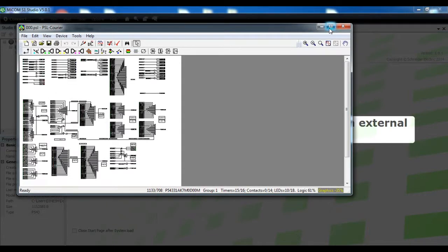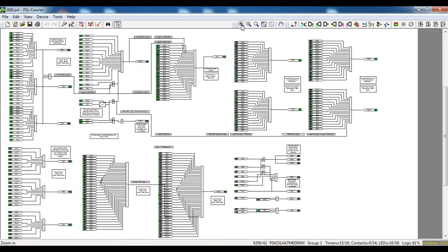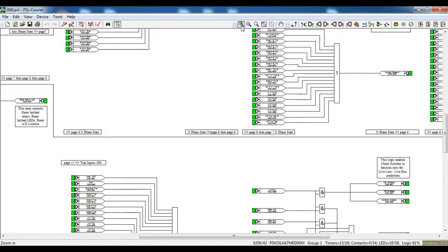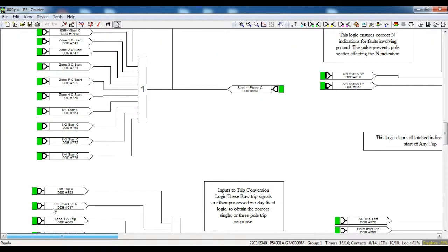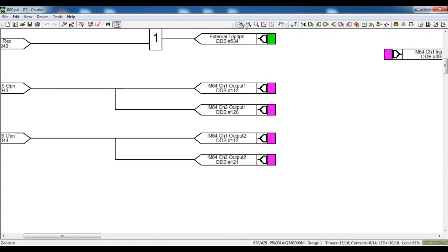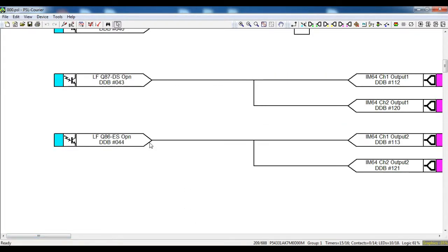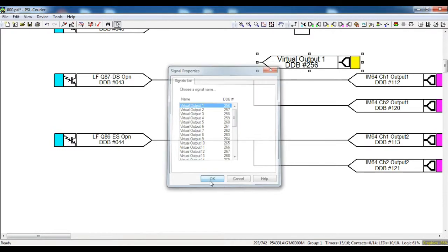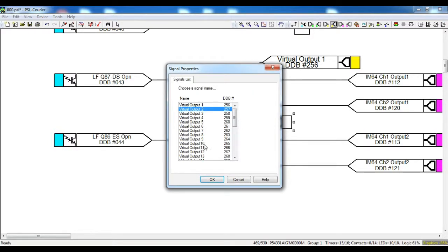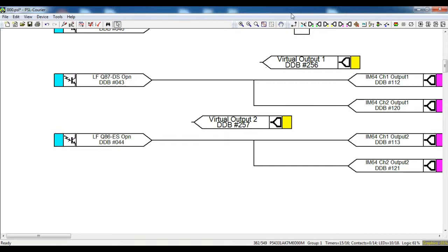First open Micom S1 Studio and click on the PSL logic sheet. Now configure the isolator for the input. I am going to map one virtual output over here. For isolator Q87 I am assigning virtual output 1. And isolator Q86 ES switch I am assigning virtual output 2. After assigning, save and close this window.